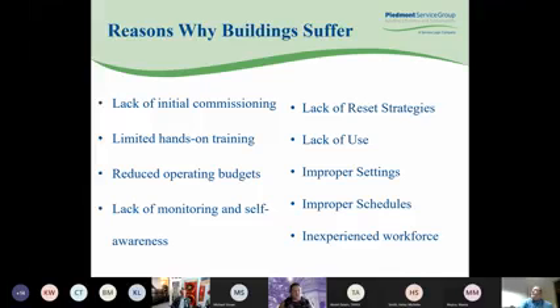So common opportunities with building control systems are lack of reset strategies for discharge air temperature and duct static pressures in air handlers, chilled and hot water temperature resets, differential pressure resets on chilled and hot water distribution loops, lack of use of occupancy sensors for common areas, faulty sensors or sensors in wrong locations, or night setbacks aren't used. We all like to walk out and forget to turn systems back. Improper settings: heating and cooling set points, outdoor air during morning warm up, dead bands that are too far apart or too close, improper schedules for air handlers and fans, and exhaust fan operation.